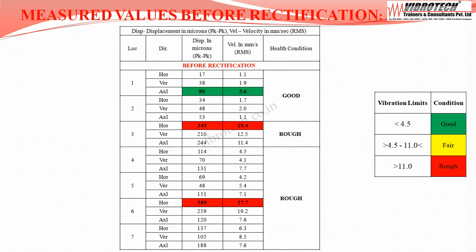Vibration data was collected. The vibration values are maximum at motor non-drive end axial: velocity up to 3.6 mm/s rms with displacement of 80 microns peak to peak. At pulley free end bearing horizontal: velocity up to 19.4 mm/s rms and displacement of 345 microns peak to peak. At low pressure cylinder bearing horizontal: velocity up to 27.7 mm/s rms and displacement of 589 microns peak to peak. The equipment health condition is rough.